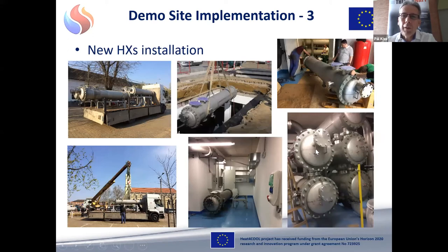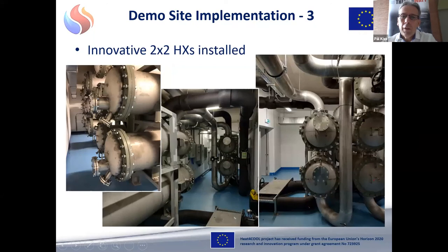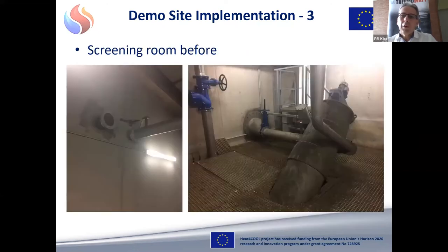They are modified. There is also an inlet to do a self cleaning of the system. And we also changed the inner part, the piping. And then we installed all stainless steel heat exchangers into the system. Those are the old screening units. So in total, the capacity of the system is 1.7 megawatt.